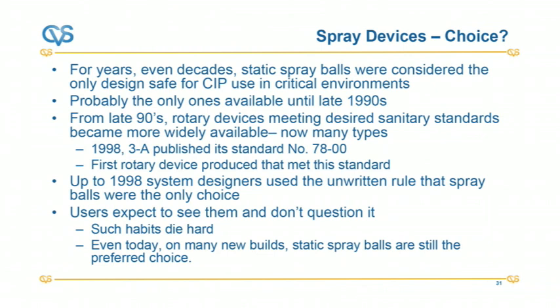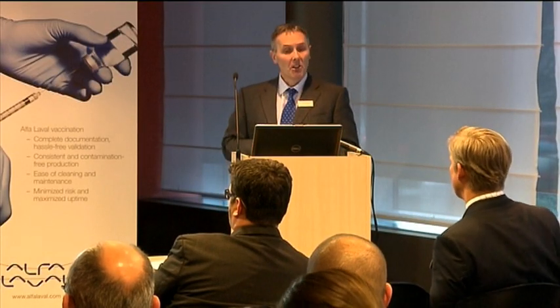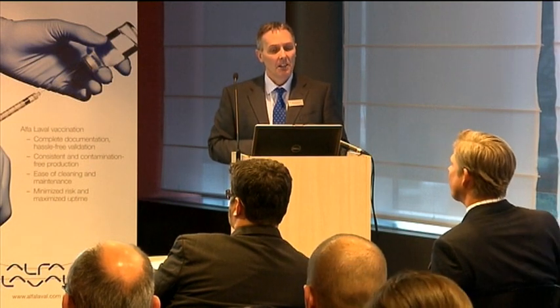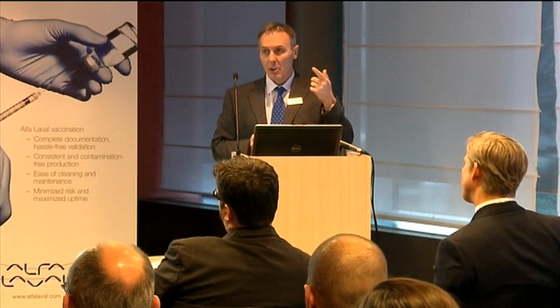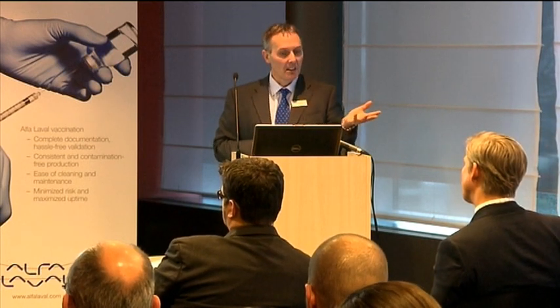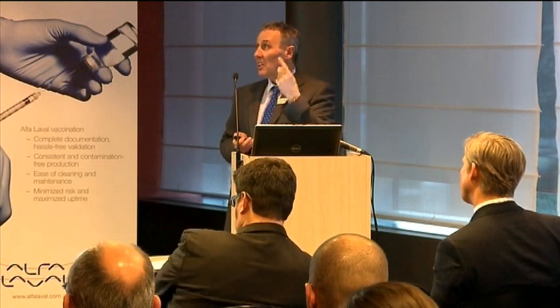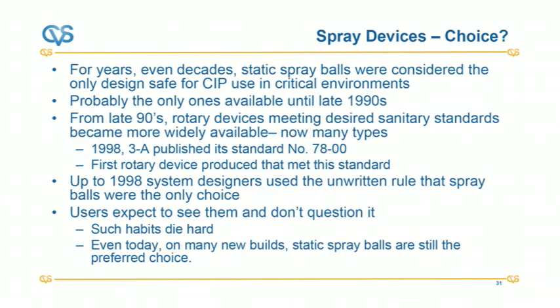Right, spray device choice. This gets a little bit more into Alfa Laval's area now. For many years, even decades, static spray balls were considered the only safe option for CIP use in critical environments, and probably really the only ones available until the late 90s. From the late 90s, 1998, some rotary devices that actually met sanitary standards became available. From then on, they became more and more available and more widely used. There's a 3-A standard that the first rotary spray device met.